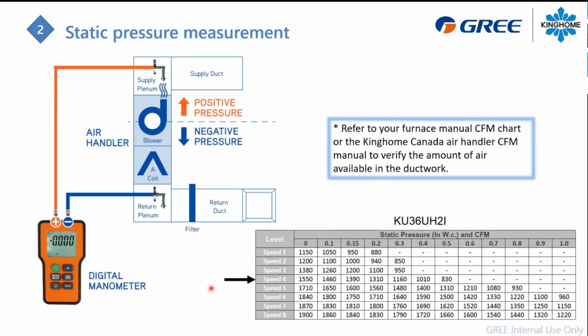Next thing here, when your installation is done, an important thing is to take your static pressure measurement. This is very important. You need to know exactly how many inches of water column you have in your ductwork when the unit is installed. So if it's an air handler, your A coil will be on the return side. If it's a cased coil, it will be in the supply plenum. But at this point, it doesn't matter which one is first, the coil or the blower. You need to have a digital manometer to be able to measure the return air static pressure and the supply air static pressure.